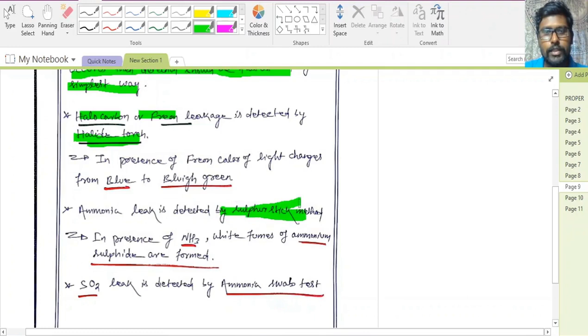Then ammonia leak is detected by the sulfur stick method. In the presence of ammonia, white colored ammonium sulfide is formed. So ammonia leak is detected by the sulfur stick method. Then sulfur dioxide leakage is detected by the ammonia swab test. So these are the leak detection methods for different types of refrigerants.